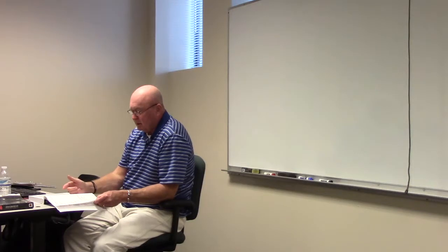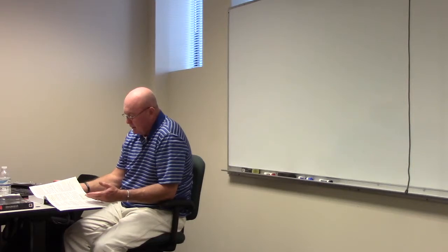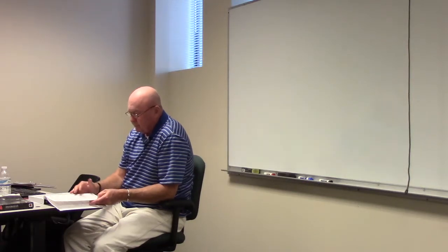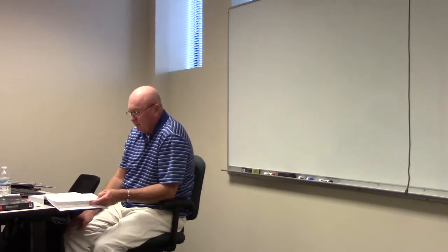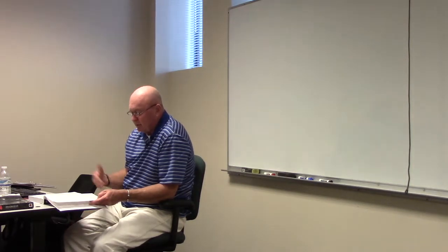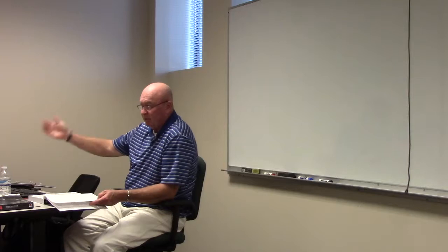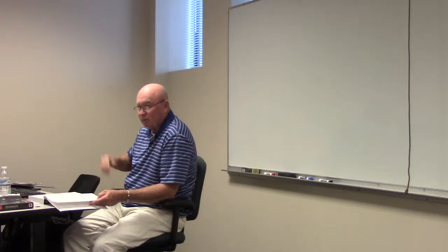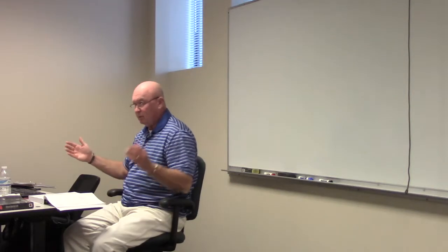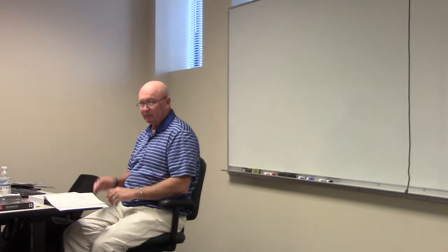All right, so, and the way they want us to do it, it says here either phase A or C would be, we can see here, we got A or C is 20.8 amps. Y'all see that there on figure 10? Okay. The receptacles, it says how many of them are there. And notice what they did. They put the load on the neutral too. You see what they did there? They put the same load. Okay. That would be, because that's worst case. Worst case, you can take that whole load and you can put it on a neutral. Worst case, for a phase.